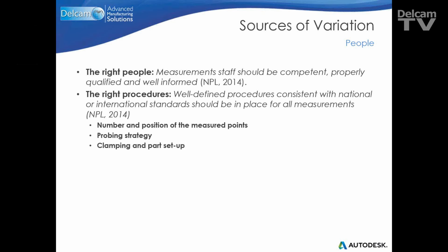Now obviously the manufacturers try and mitigate this these days by putting either friction drives or ratchet drives onto the micrometers to cut off, if you like, the applied pressure of the user of the gauge. But it's a key thing with all of these sources of variation we're going to talk about. You can never eliminate those variations. You can only mitigate them. You can only dampen their effect, or at least take away the mass of their effect. So, for example, a friction thimble or a ratchet thimble on a micrometer is taking away the mass of the extra force, if you like, that the operator could apply through that device. But it's still not completely removing it.